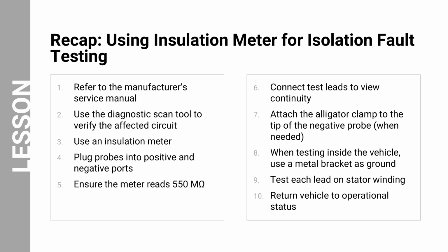Let us recap what we have covered in the 10 steps on how to use an insulation meter to conduct isolation fault testing. Step 1. Refer to the manufacturer's service manual. Step 2. Use a diagnostic scan tool to verify the affected circuit. Step 3. Use an insulation meter to test the voltage. Step 4. Plug the probes into positive and negative ports. Step 5. Ensure the insulation meter reads 550 mega-ohms. Step 6. Connect the test leads to view continuity. Step 7. Attach the alligator clamp to the tip of the negative probe when needed. Step 8. While testing inside the vehicle, use the metal bracket as a ground. Step 9. Test each lead on the stator winding. Step 10. Return the vehicle to operational status.